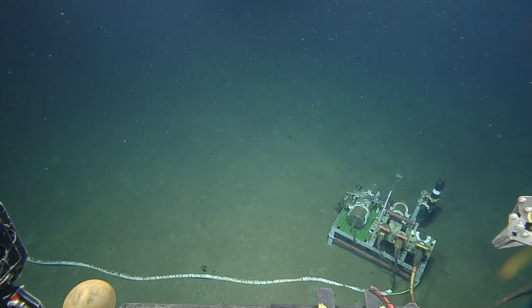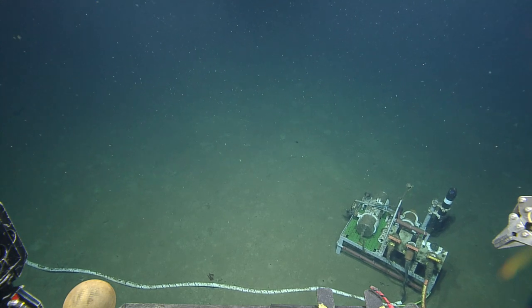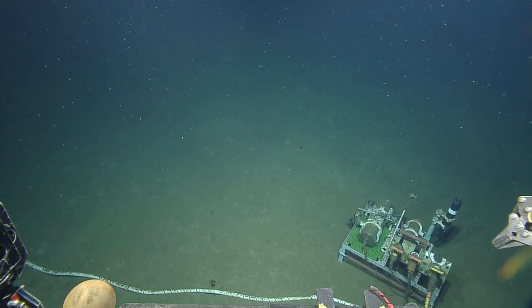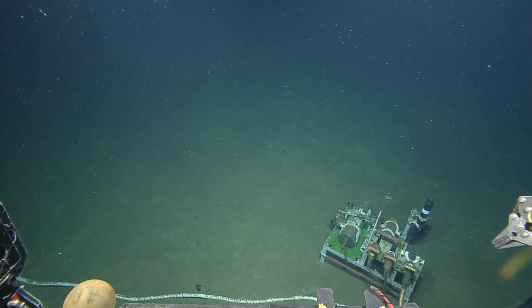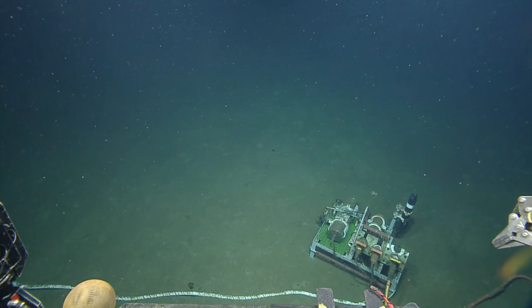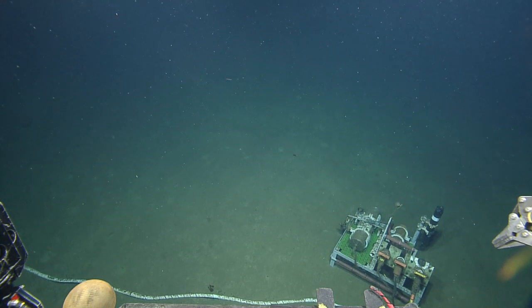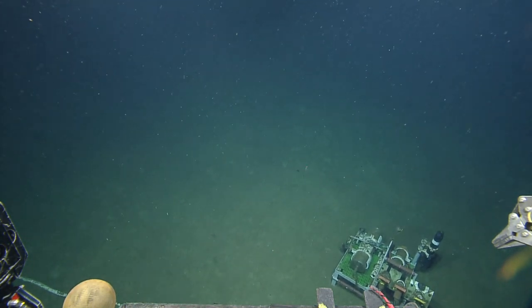The reason we're not doing any work now is because we don't have a dummy plug for the pins on the platform side, so we're just trying to minimize how much that's exposed, but that shouldn't take too long once we're in position for that. Do we need to shut the battery off? Yes. So we could turn the battery off now. That's something we could do, in advance. If you are comfortable doing that, we can do that now.